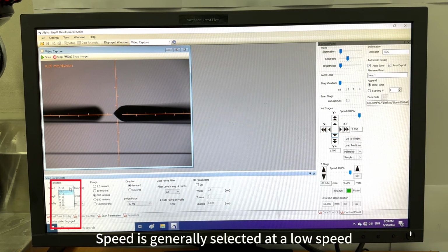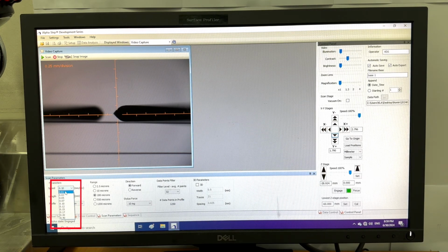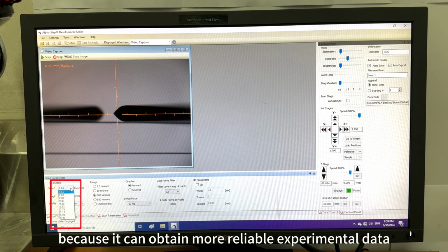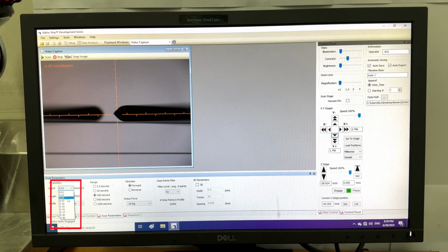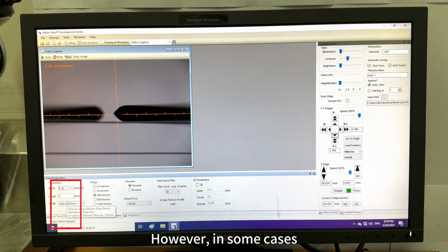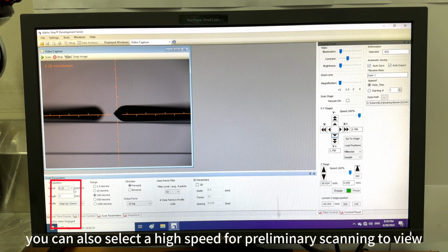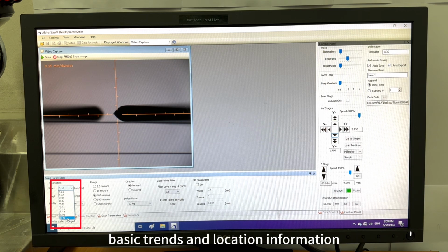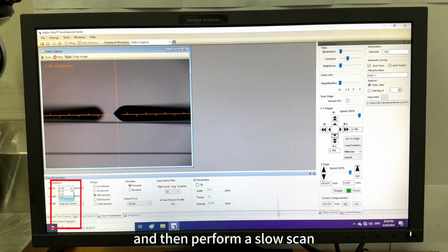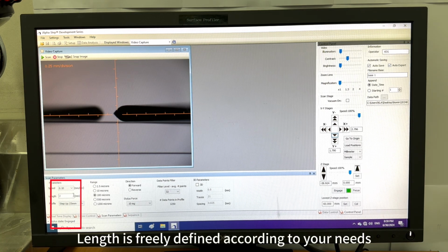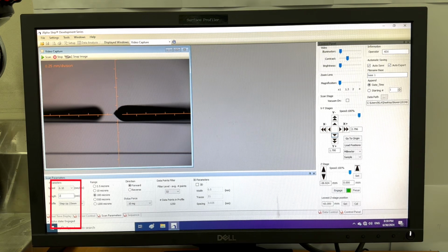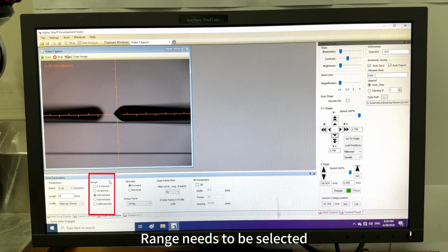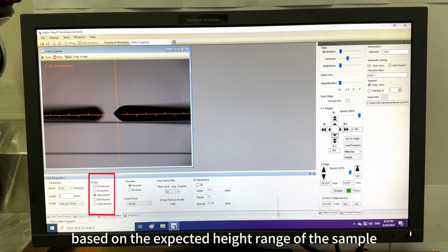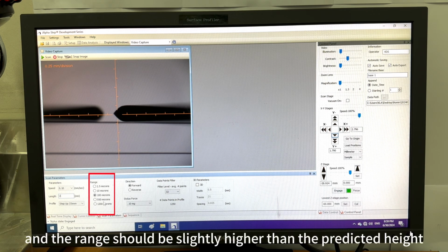Speed is generally selected at a low speed, because it can obtain more reliable experimental data. However, in some cases, you can also select a high speed for preliminary scanning to view basic trends and location information, and then perform a slow scan. Length is freely defined according to your needs. Range needs to be selected based on the expected height range of the sample, and the range should be slightly higher than the predicted height.